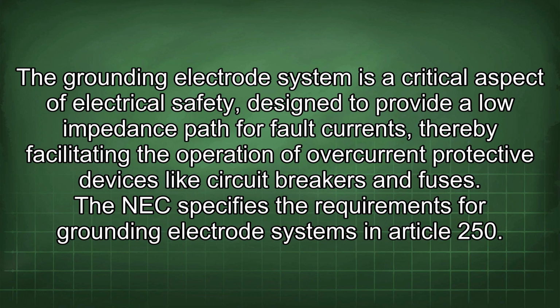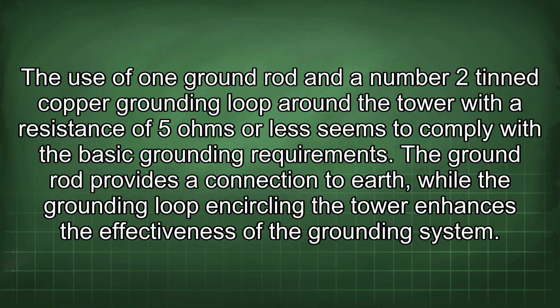The grounding electrode system is a critical aspect of electrical safety, designed to provide a low impedance path for fault currents, thereby facilitating the operation of overcurrent protective devices like circuit breakers and fuses. The NEC specifies the requirements for grounding electrode systems in Article 250. The use of one ground rod and a number 2 tinned copper grounding loop around the tower with a resistance of 5 ohms or less seems to comply with the basic grounding requirements.